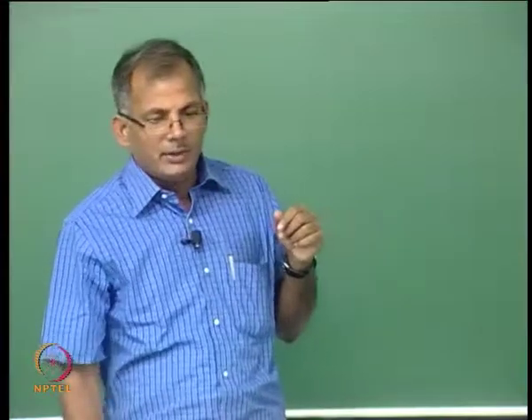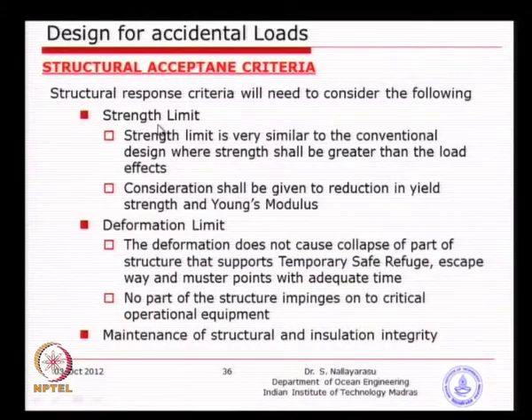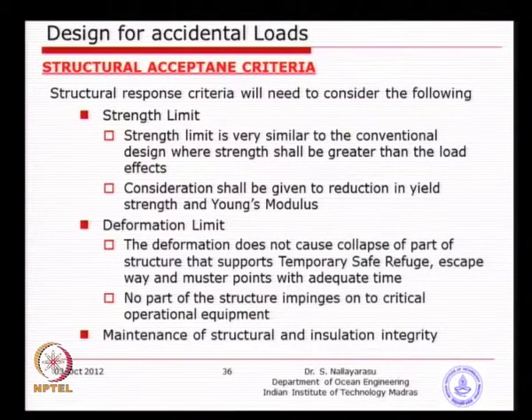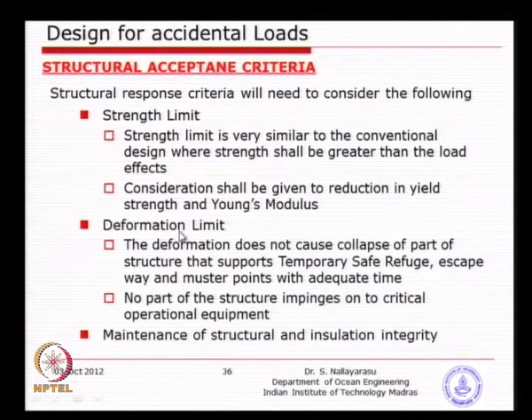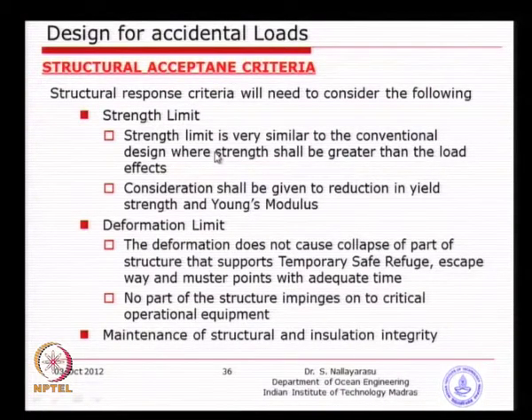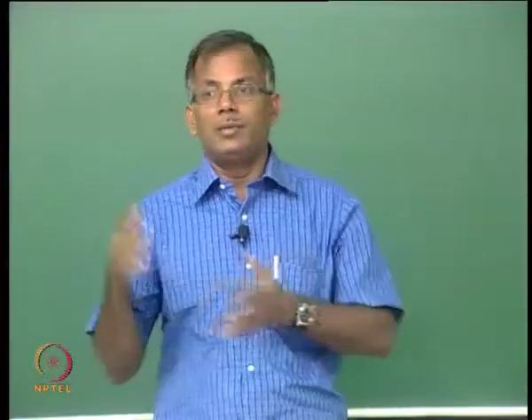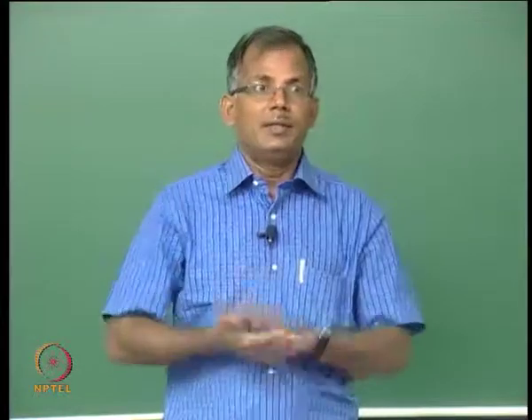Acceptance criteria include two things: structural strength limit — no disintegration, walls must remain attached — and deformation limit, to ensure large deformation does not affect neighboring structures or facilities. The strength limit is design capacity versus load effects. How to deal with it — allowable stress design, LRFD, or another method — needs to be decided.